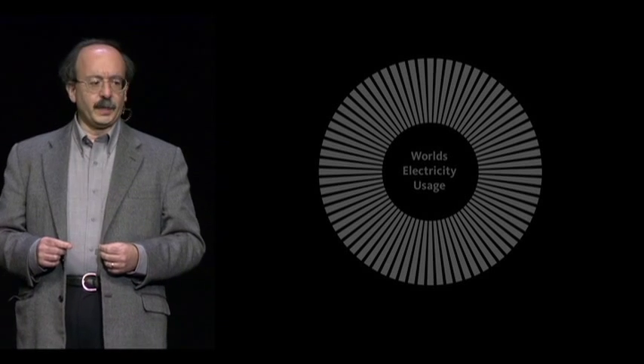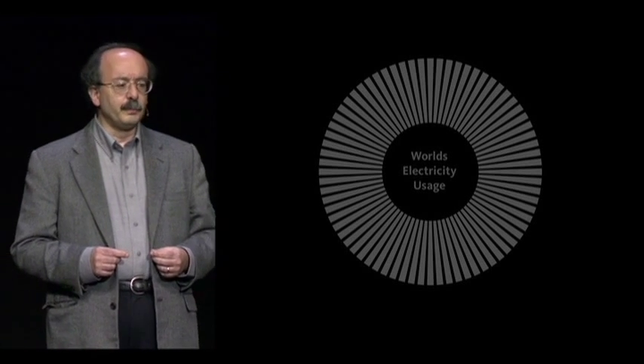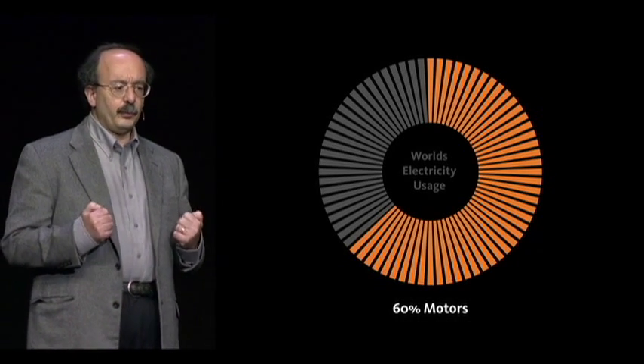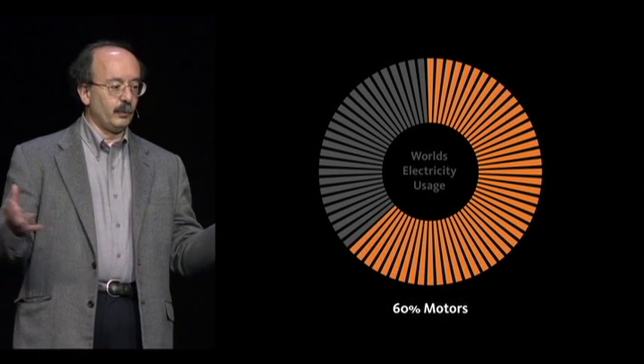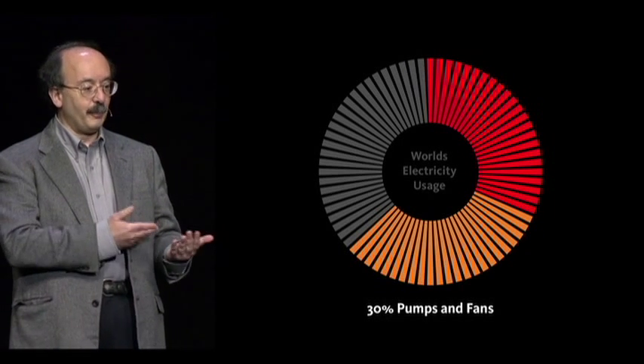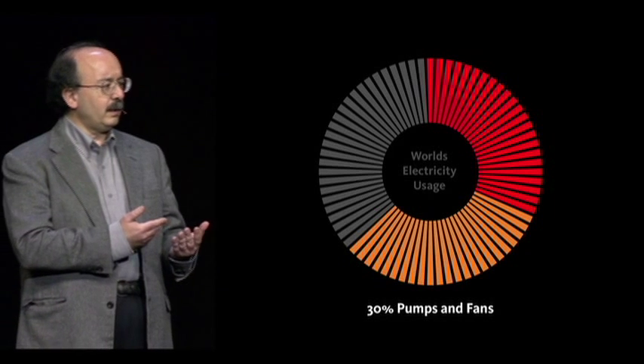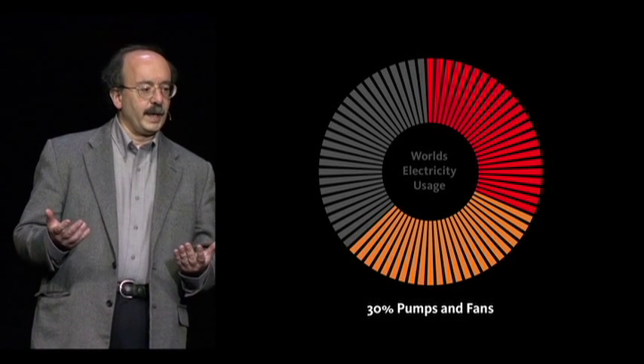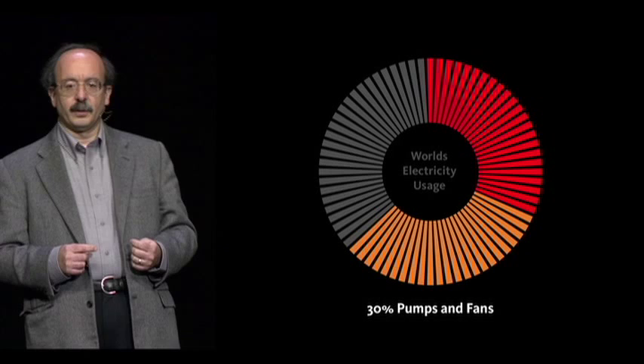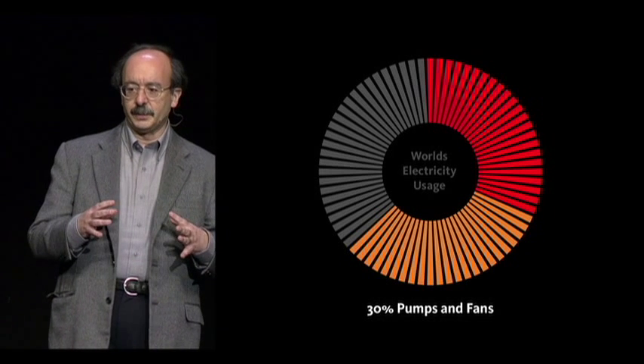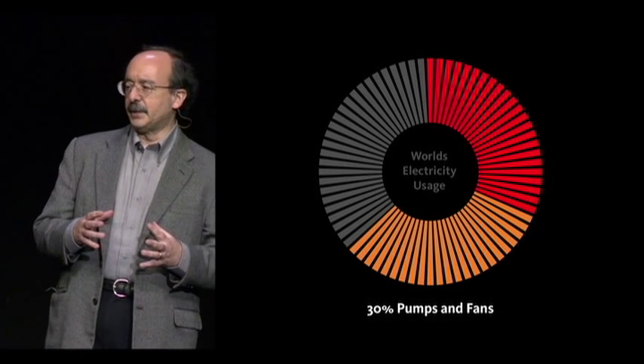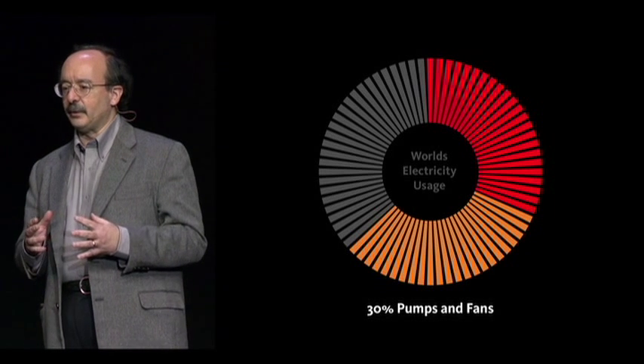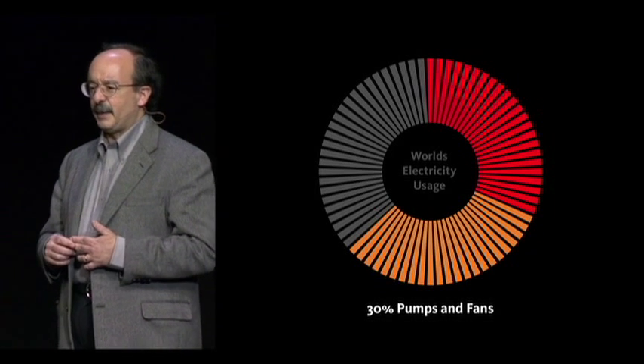The same approach of integrative design works great in industry too. For example, three-fifths of the world's electricity runs motors. Half of that runs pumps and fans. We can save about half of all the motor energy with a one-year payback by integrating 35 retrofits to the motor system, and 28 of those retrofits are free byproducts of the first 7. So it pays back in about a year or less.